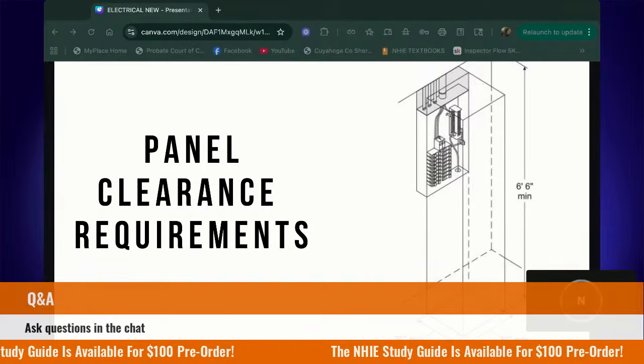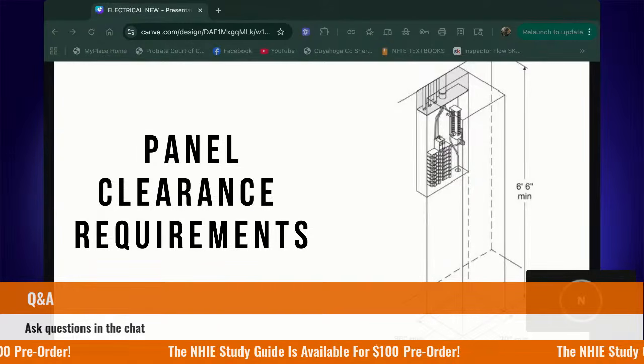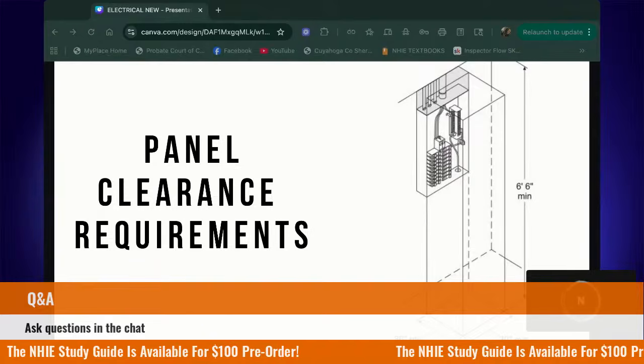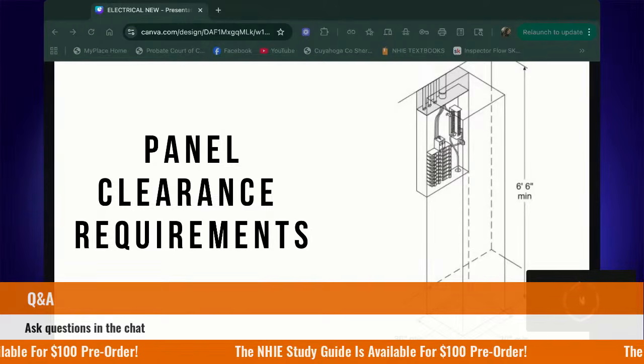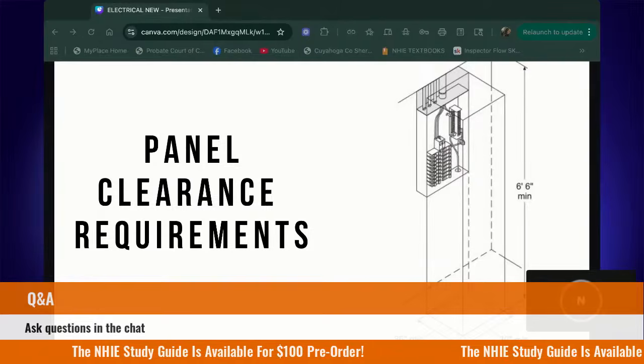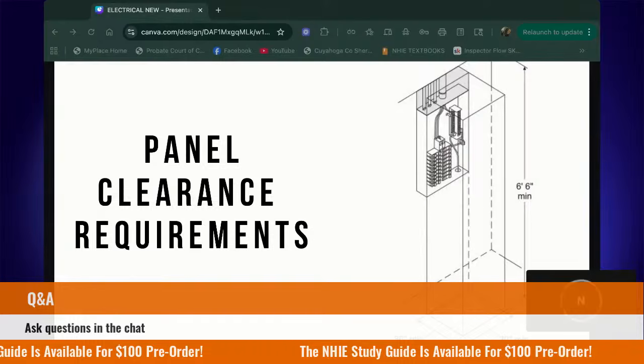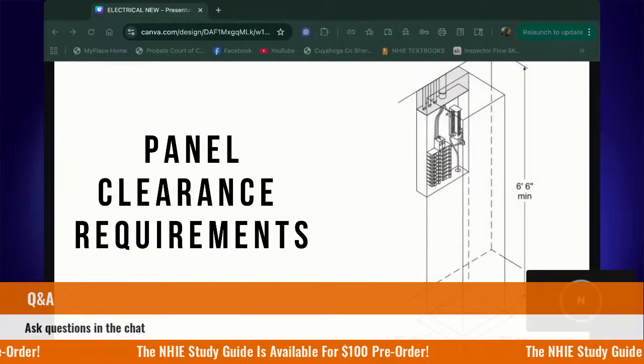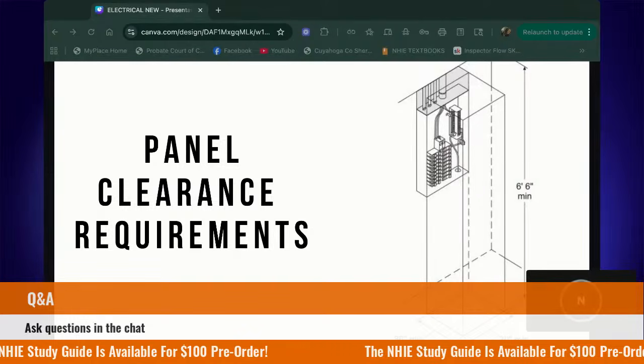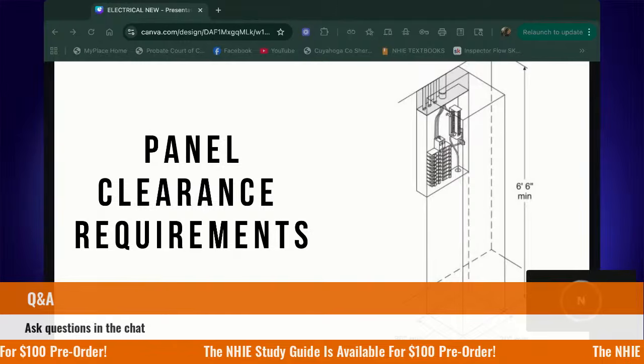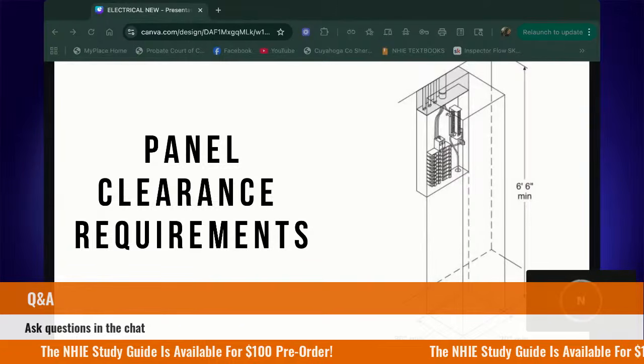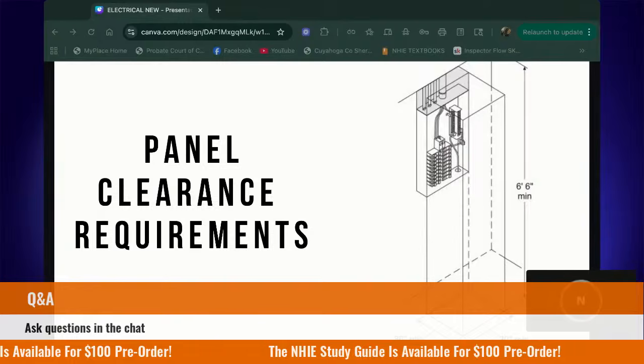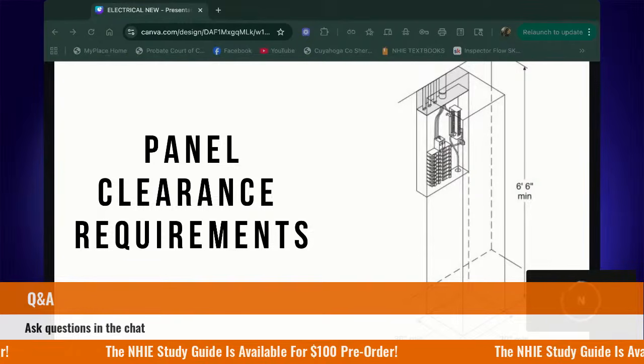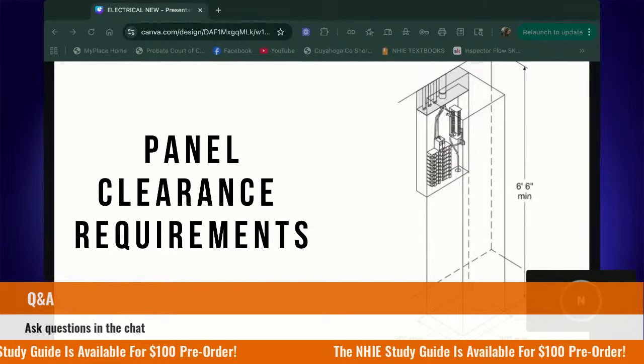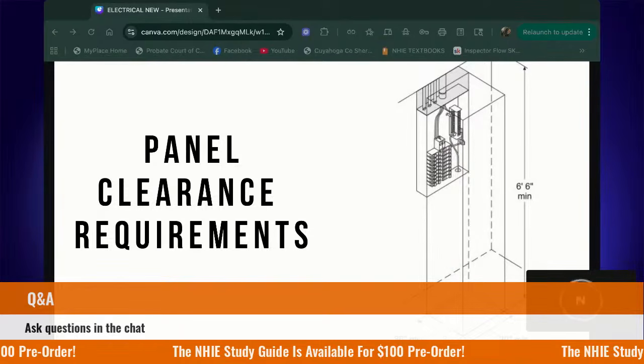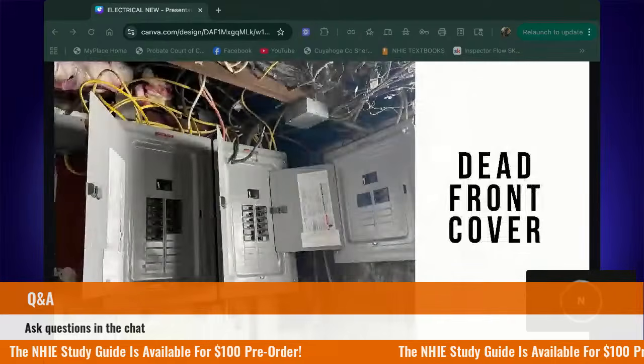Okay? So some of your state SOPs might require you to open it, but ultimately it comes down to the decision that you make about the safety of yourself first, and then also the building, right? We have a responsibility to look out for our physical safety, as well as the safety of the building. We don't want there to be any sort of electrocution. We don't want there to be any arc flashes that could start a fire. We don't want any of that. So you will have to assess the situation and make a decision on whether or not it makes sense for you to open the panel.